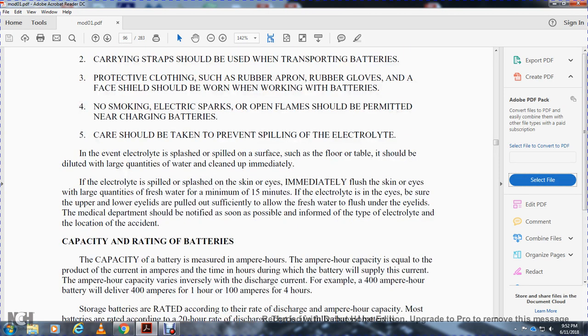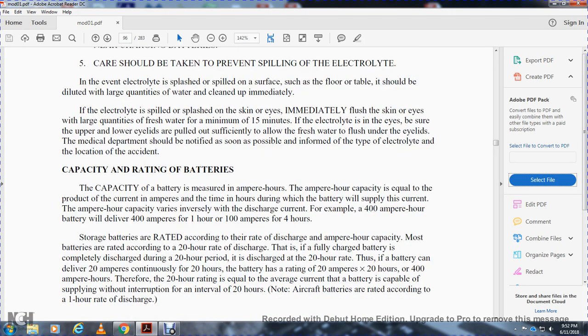If electrolyte splashes or spills on a surface or floor, dilute with a large quantity of water and clean up immediately. If electrolyte splashes on skin or in the eyes, immediately flush with a large quantity of fresh water for a minimum of 15 minutes. If electrolyte is in the eyes, be sure upper and lower eyelids are pulled out sufficiently to allow fresh water to flush under the eyelids. Medical department should be notified as soon as possible; inform them of the type of electrolyte and location of the accident.